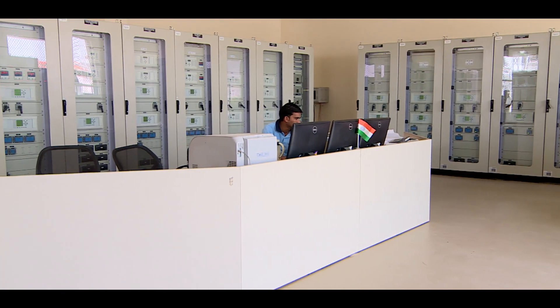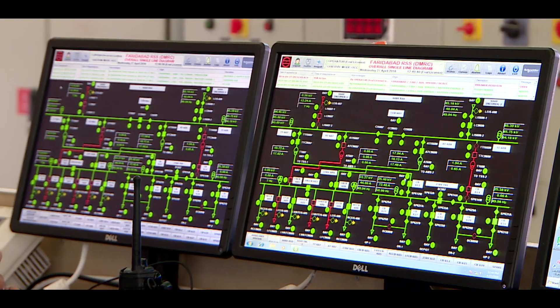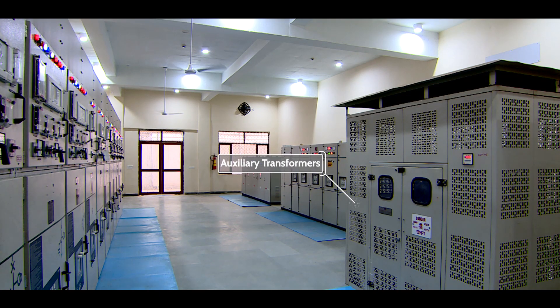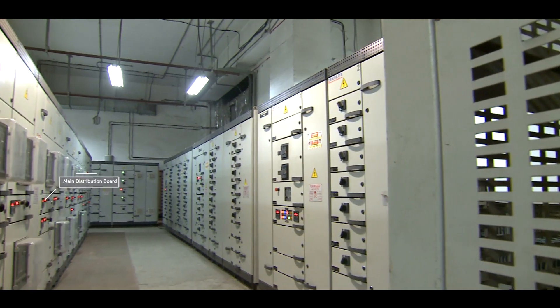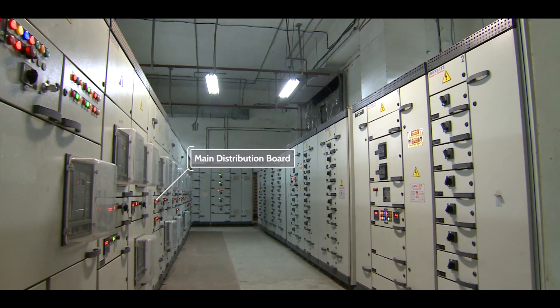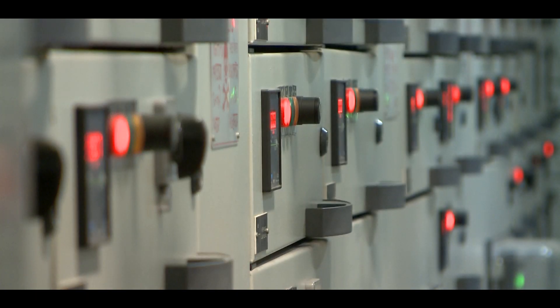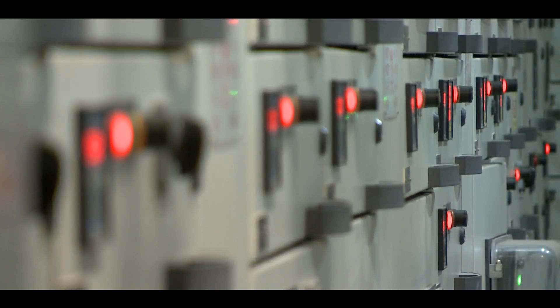This power supply received at 33 kV is stepped down to 415 V at the station through auxiliary transformers and supplied to the main distribution board or MDB, which is installed in a room called auxiliary substation or ASS.